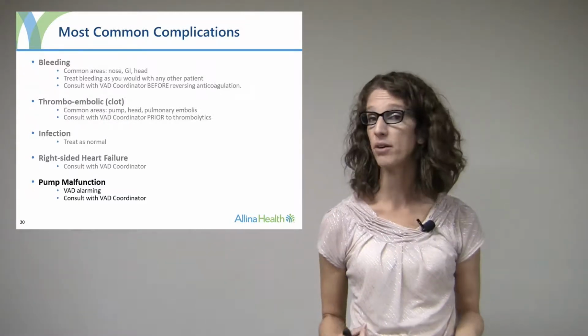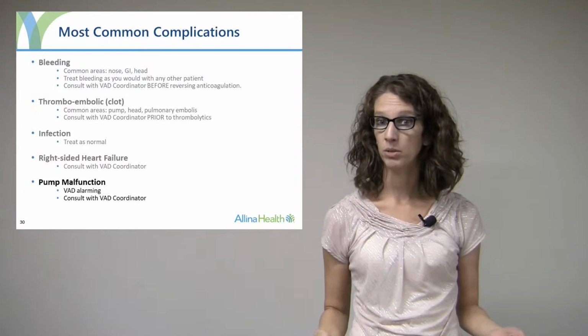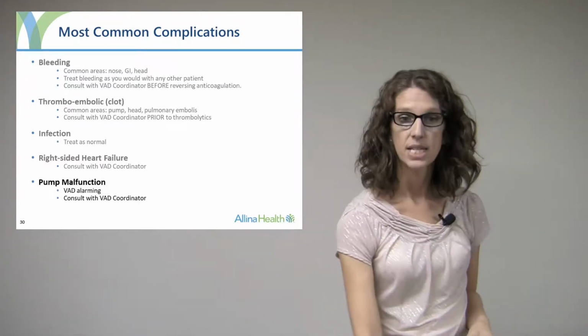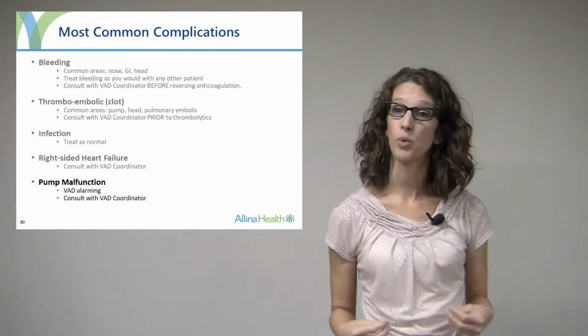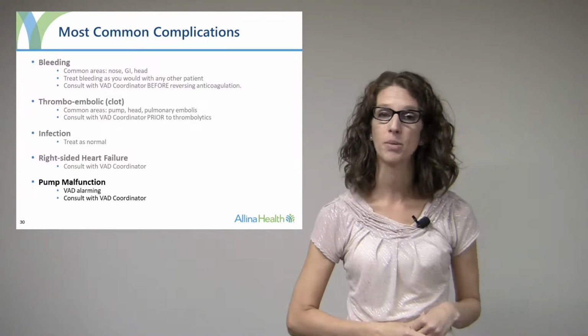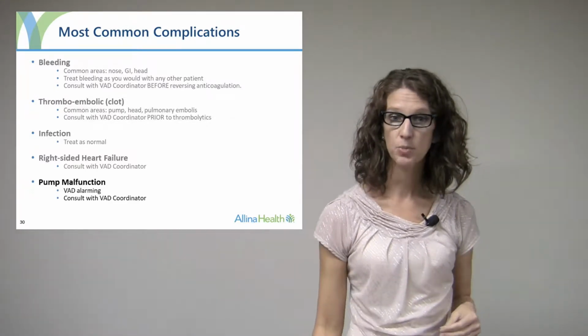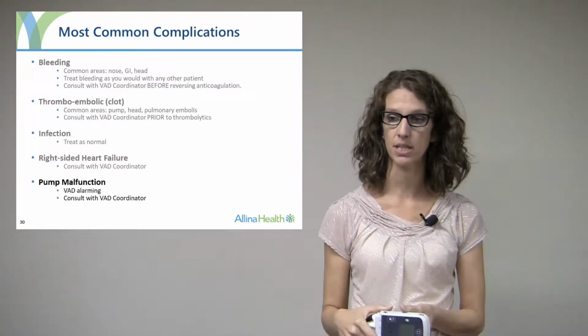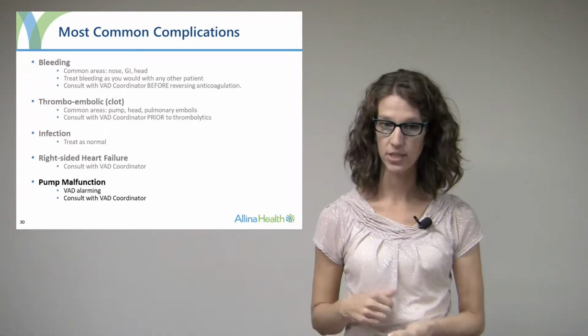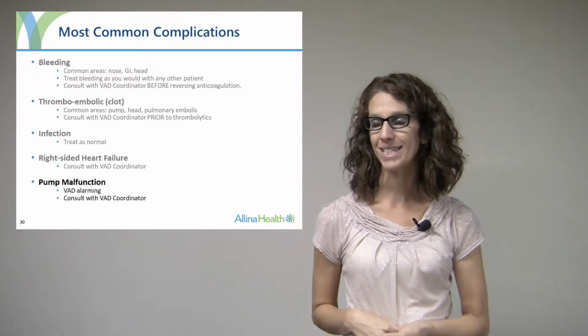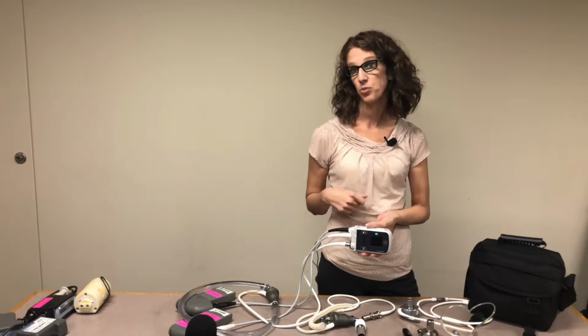Though it's a very rare complication, the VAD will be alarming. Sometimes the VAD is alarming and it's still running. Sometimes the VAD is alarming because it is off. The easiest place to assess that in the HeartMate system is going to be this green circle. If the green circle is on, the pump is running.